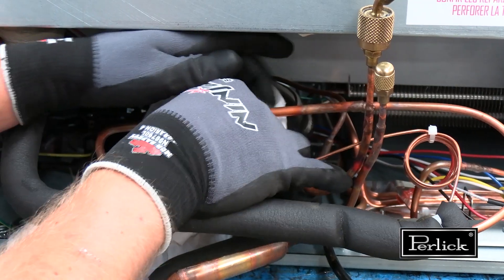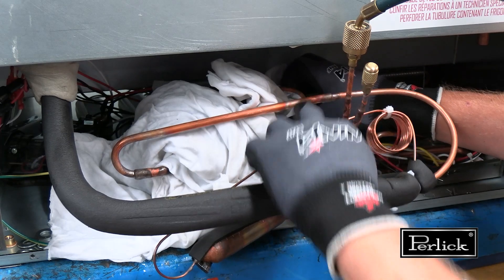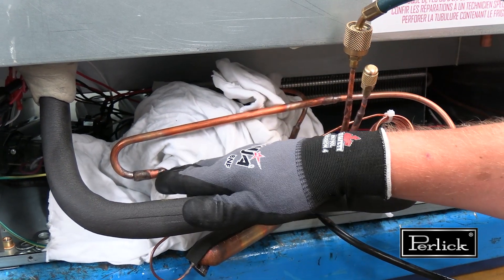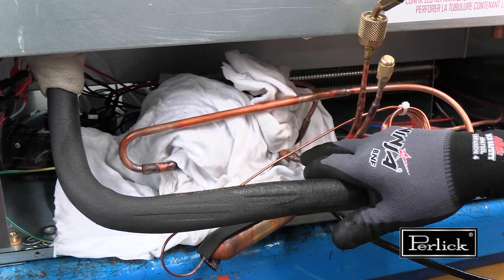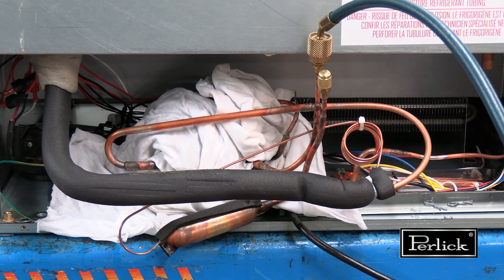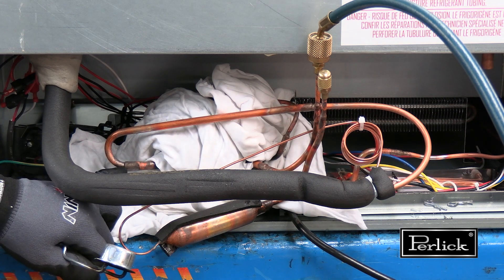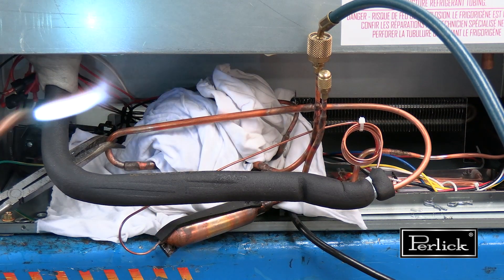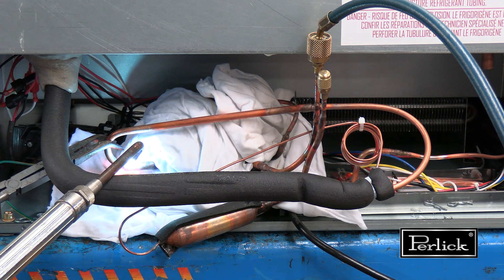Allow for a minimum clearance of approximately one half inch to the braze joint you are undoing. Using a neutral flame, begin unbrazing the suction line going into the compressor. Then remove the discharge line leaving the compressor. Apply heat to the fitting, protecting the component from being damaged.